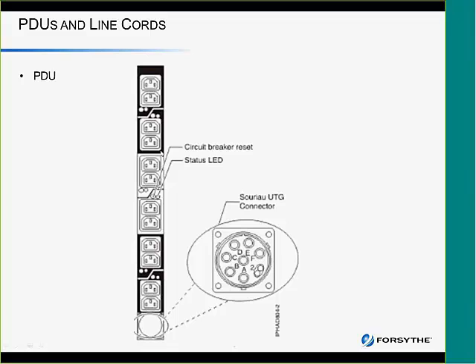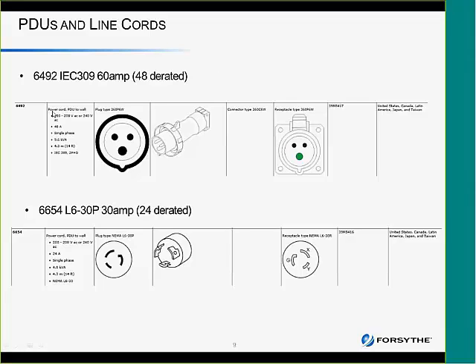So that's one of the reasons it's very, very important to pay attention to what is plugged in where and how often. These are pictures of the actual plugs for that 6492, 60 amp, and 6654. I get asked all the time by electricians, well, what's the receptacle, what's the connector type? This has all that information in here. So it's quite a useful little picture.